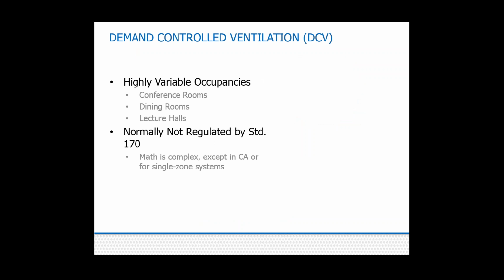So also for your non-healthcare spaces, demand-controlled ventilation can save quite a bit of energy. It's becoming required for a lot of these spaces more and more in the newer energy codes, but your conference rooms, your dining rooms, your lecture halls, normally this is not your spaces that are regulated by standard 170 or the FGI. In multiple zone systems, the math can get kind of complex, except I think if you're in California, there's a rule about what parts per million you should set it at. Or if you're a single zone system, the math also gets pretty simple. But it can be a big energy saving feature. Next slide, please.